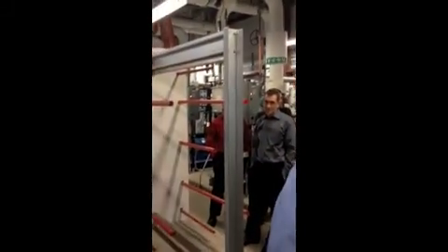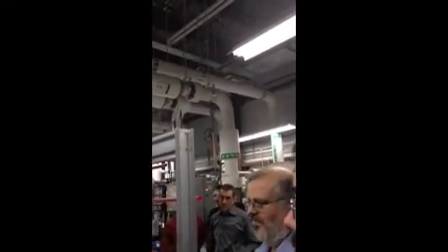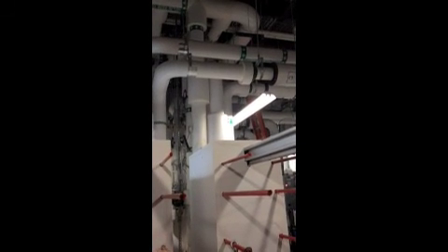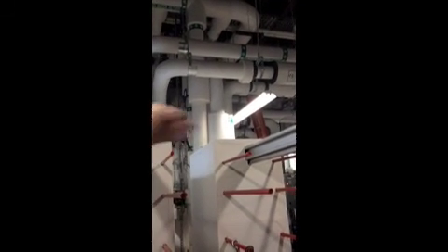It's not done with a mixing valve. The way it's done, the secondary pumps are on VFDs, and the primary pumps run full speed in the chiller room, and by varying the speed of the secondary pumps, you regulate the mix. So there's actually what's called a bridle loop up there, where it either mixes with the water from the heat exchangers or it just loops back to the chillers.